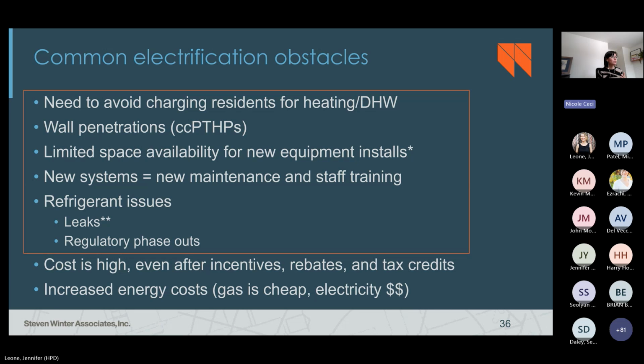Those are obstacles that we think we can overcome or at least make a little bit less difficult by going with the hydronic solution. First one, we do avoid charging residents for heating and domestic hot water because the terminal units use very little power for heating. And VRF is similar in that regard. The difference is that with this solution, we have a lot of options for keeping most of the cooling cost on the residents' meter in the hydronic approach. And then domestic hot water stays on the house meter.